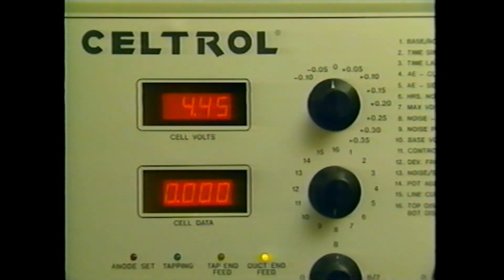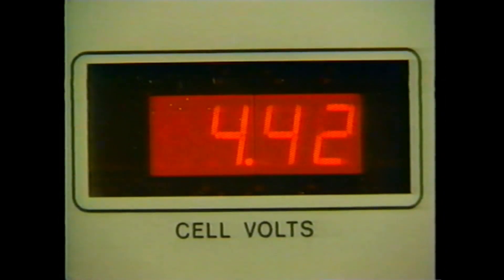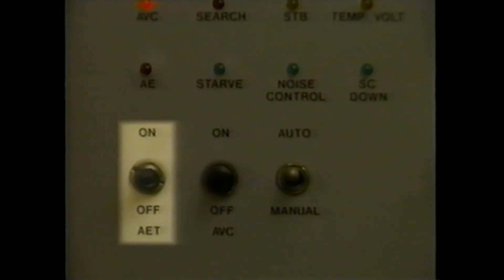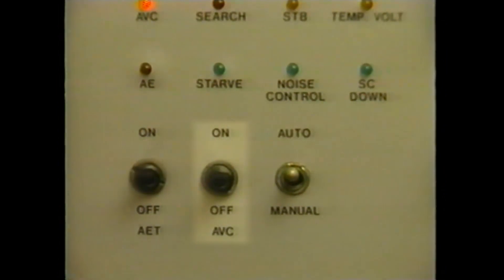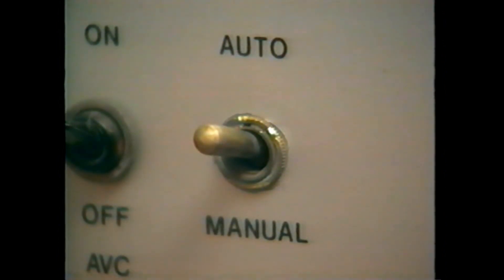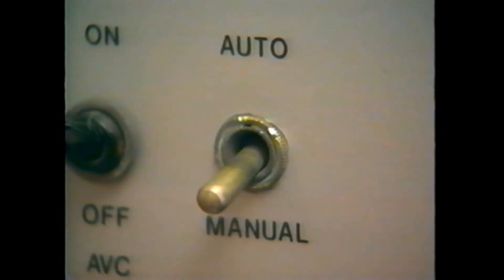There are two displays on the Celtrol panel at each pot. The top display is the cell voltage reading; the bottom shows the selectable 4-digit display. With the selector switch, the items to be displayed are chosen. The AET switch operates or disables automatic anode effect termination. The AVC switch controls whether automatic voltage control is on or off. The tap and duct end feed switches control feed at the specified ends. The brake switch, when on, allows the breaker to brake; when off, the breaker cannot. In the auto position, the computer has control of the pot; in the manual position, data continues to be collected but the pot is under complete manual control.